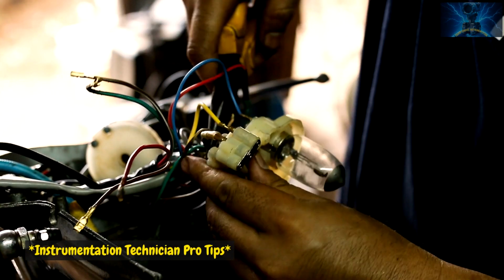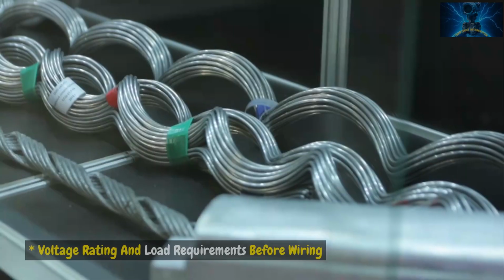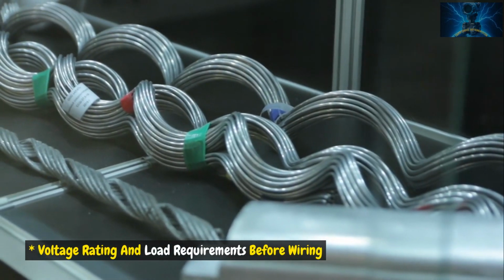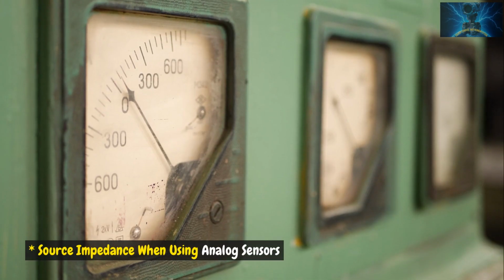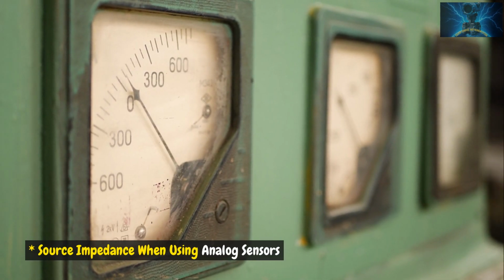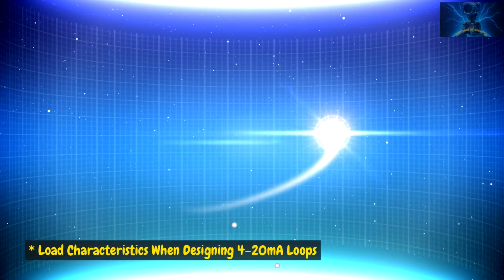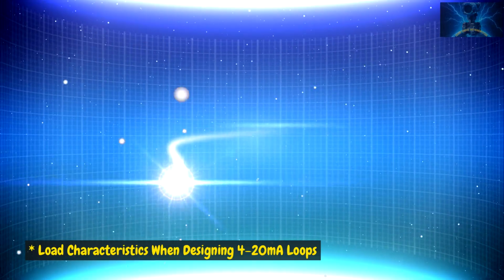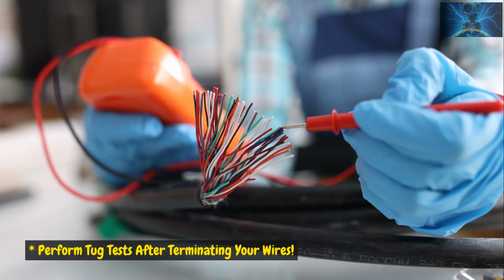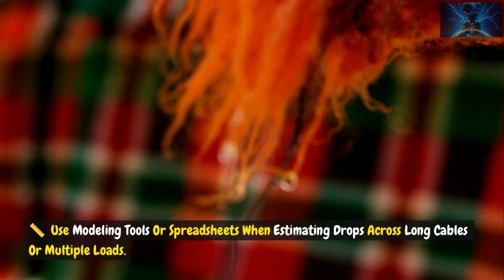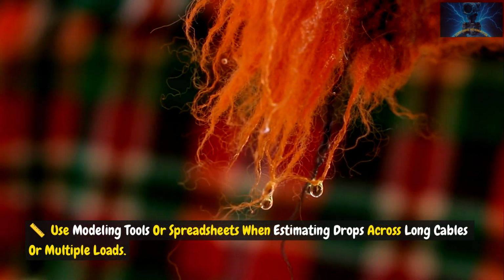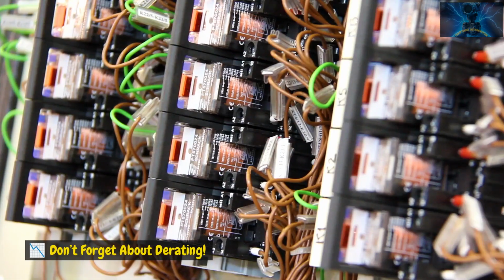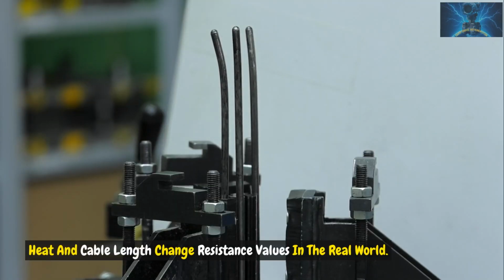Instrumentation technician pro tips. Always check voltage rating and load requirements before wiring. Check source impedance when using analog sensors. Check load characteristics when designing 4-20 mA loops. Perform tug tests after terminating your wires. Use modeling tools or spreadsheets when estimating drops across long cables or multiple loads. Don't forget about derating. Heat and cable length change resistance values in the real world.